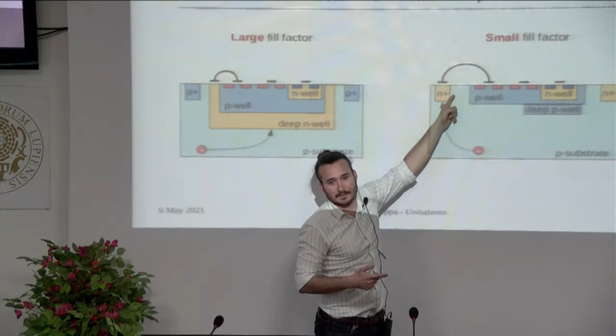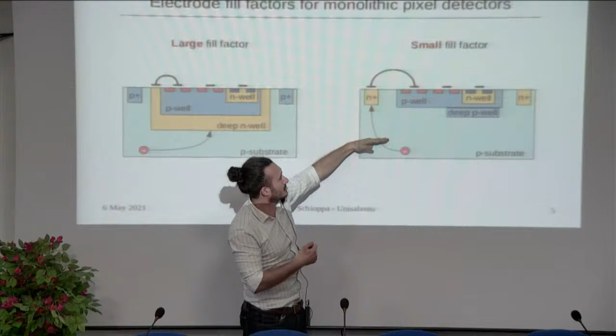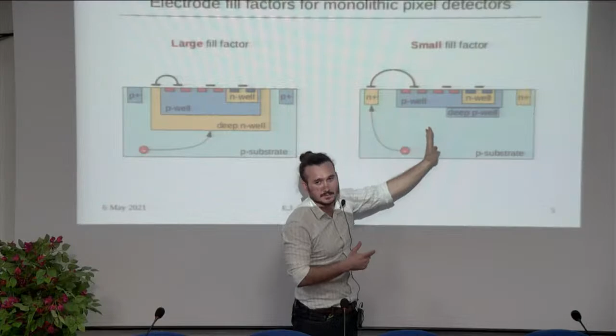The problem here is that the junction, the p-n junction that makes your detector work, that makes your electric field, that makes the charges drift and induce a signal, well, that's confined in a small region around the electrode. You can increase the voltage, the bias voltage of the junction, but at some point, the risk of reaching breakdown before actually depleting all the useful volume is quite large. Okay, so you have to be really smart to make it in such a way that you can actually deplete all this stuff.